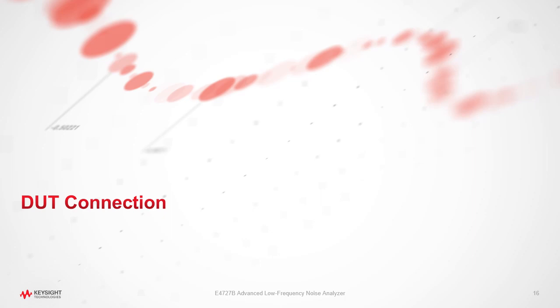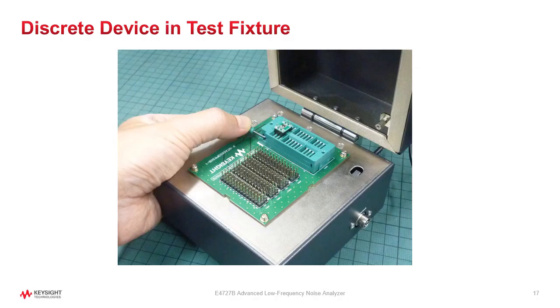Let's understand the DUT connection. A discrete device is measured with the test fixture. The test fixture has a 28 pin IC socket, and you can use a package device of up to 28 pins.